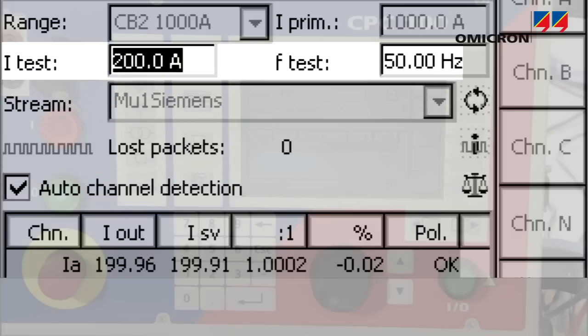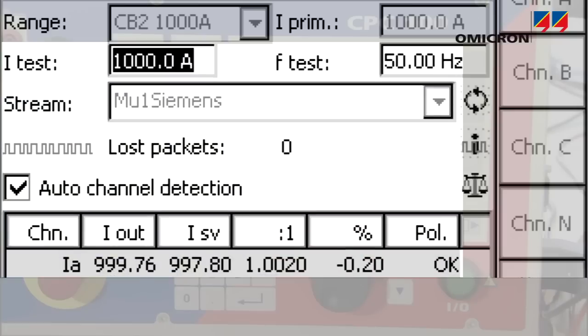When injecting primary current as set by the user, the CPC evaluates the respective stream of sampled values and displays CT ratio and polarity, just as when testing a conventional CT.